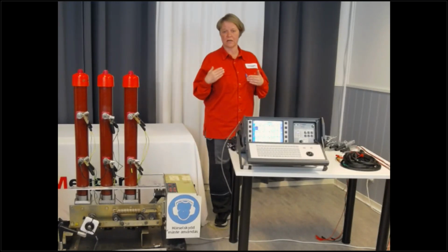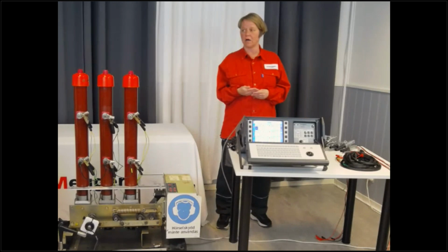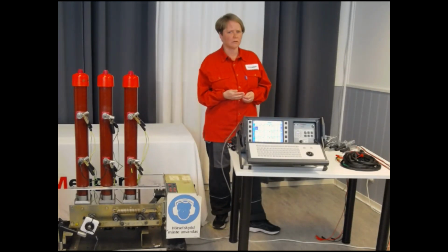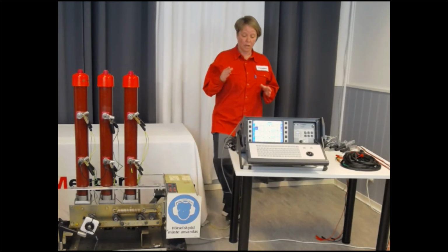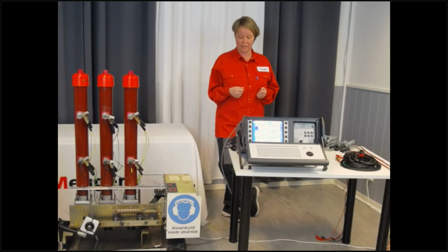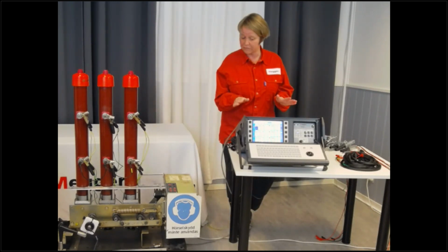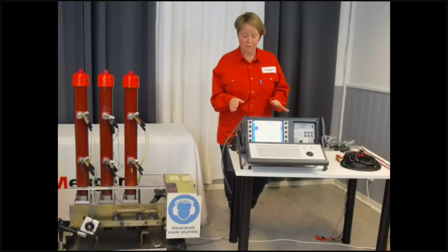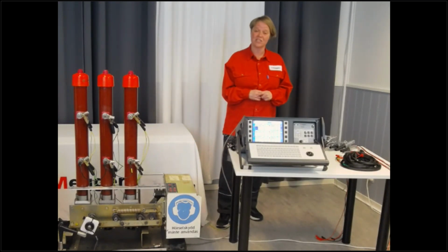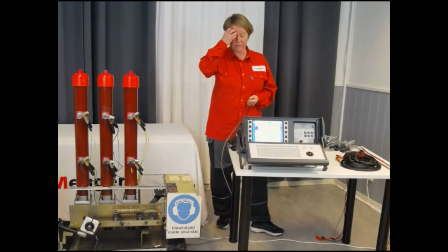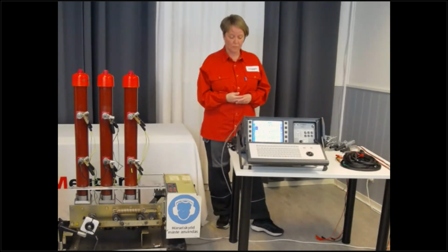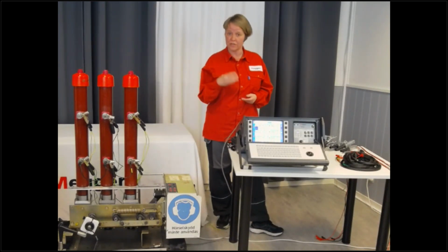This kind of timing, which we did with EGIL, has been done since, I think, the 70s at least, when we came with a product called TM1600, which is still out there, but we don't sell it anymore. That's using the same principle as EGIL. TM1800 and TM1700 can also do this kind of timing. And actually that channel is also used during the dual ground timing as the measurement reader. But to do the dual ground timing, you need an extra module.